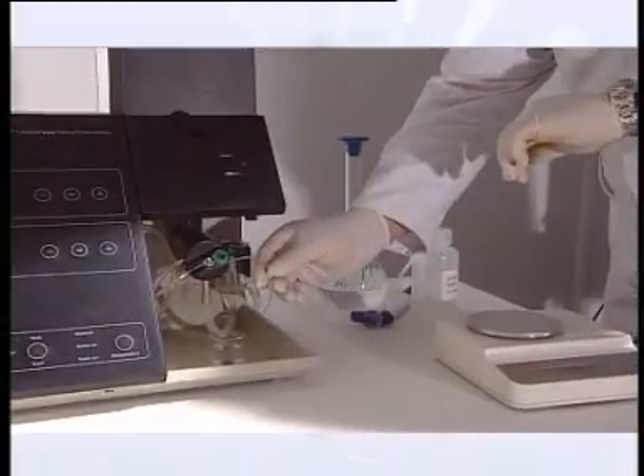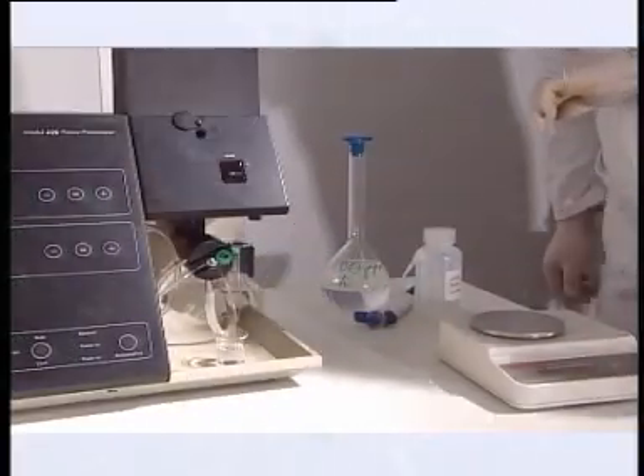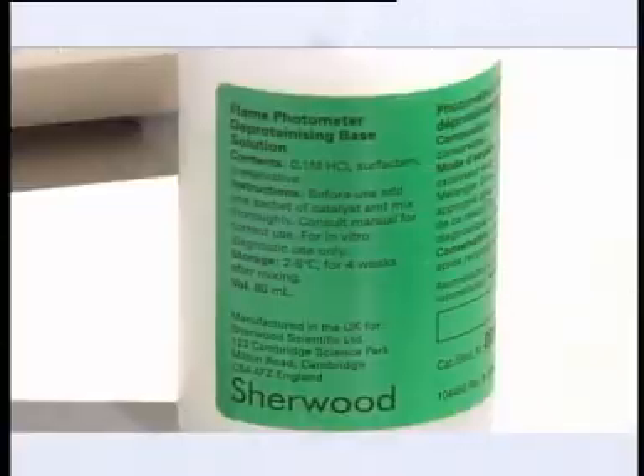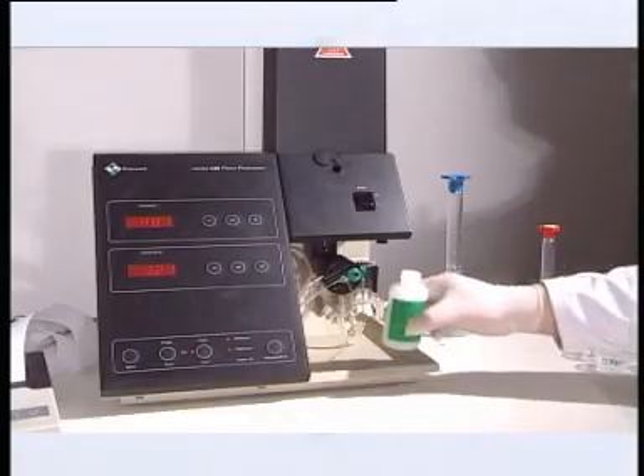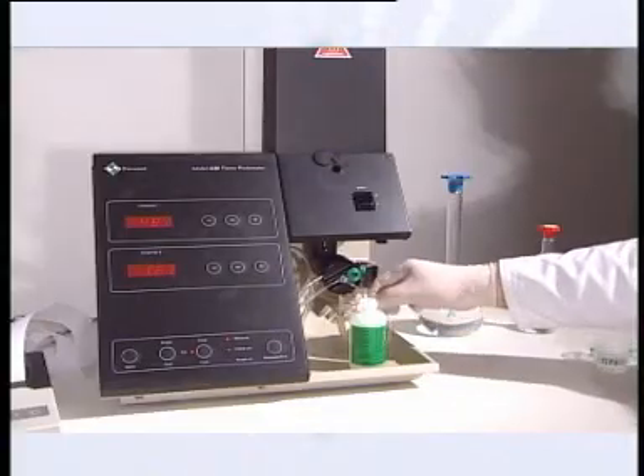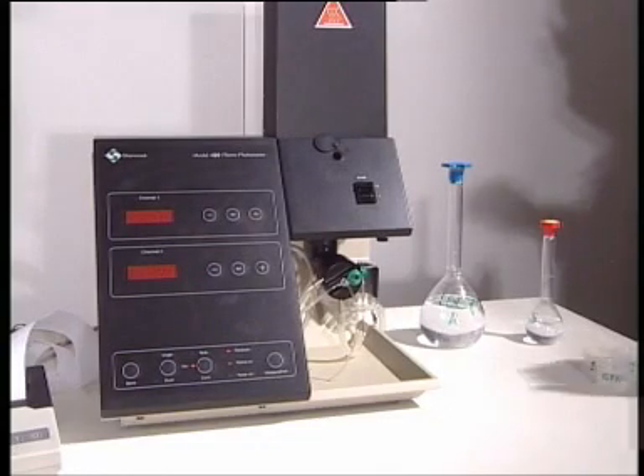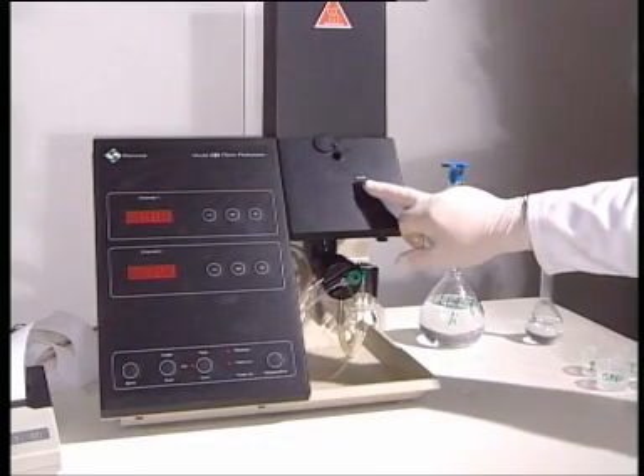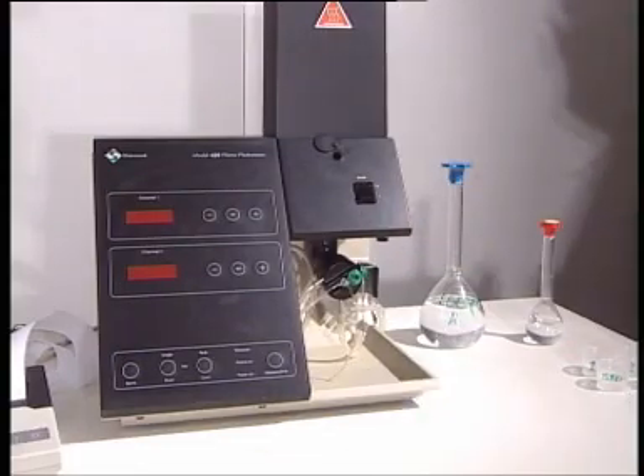When closing down the Model 420 for a long time, such as overnight, the correct procedure is to aspirate clean water, then deproteinising solution for 5 minutes to clean the mixing chamber. Then shut off the gas at the cylinder. The gas flame will continue to show for a few minutes as the gas in the tubing is burnt. Once the flame is extinguished, E61 is displayed. The flame photometer can then be switched off. Care should be taken as the top of the chimney will still remain hot.